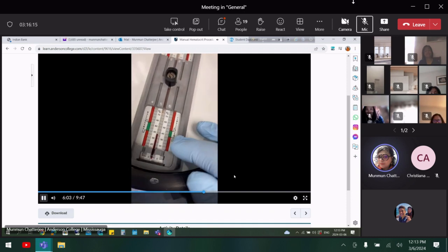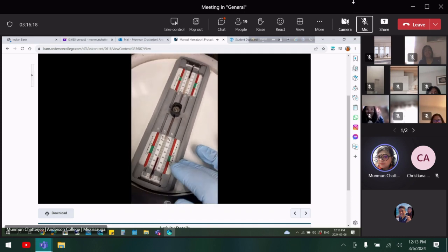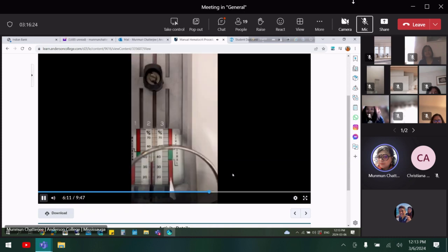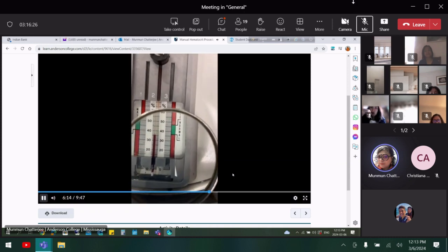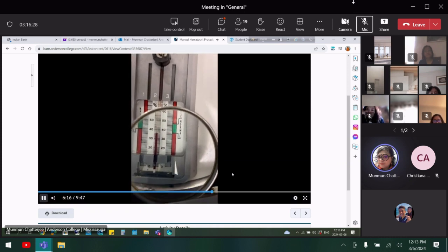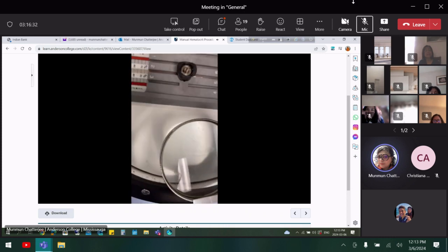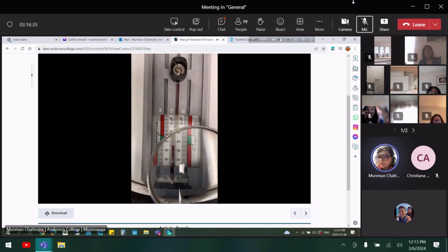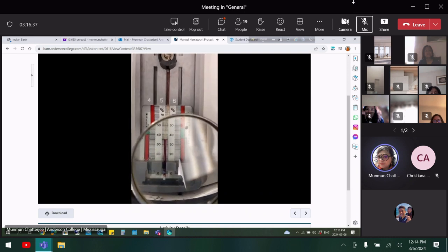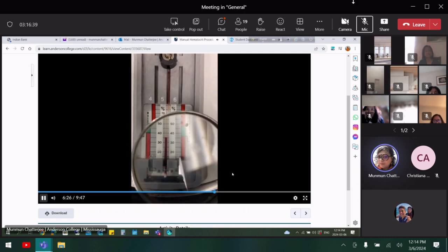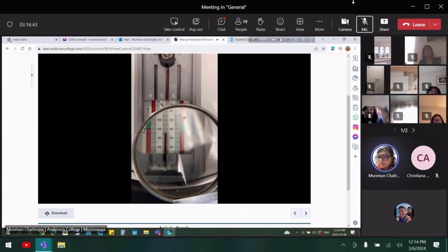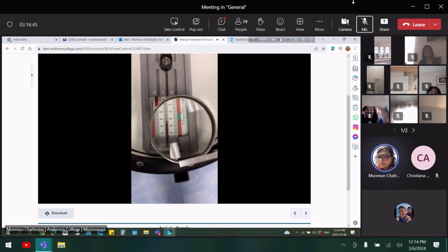However, it's a little bit old, and I'm not so sure how accurate it is. But just for example, let's see if these are within 1% of each other. So if we read this through our microscope here, we could see that it's at about 36% or 0.36 liter per liter. If we look at this one, we can see as well, it's about 35 and a half. So 0.35 or 35%. So they are within that 1%.